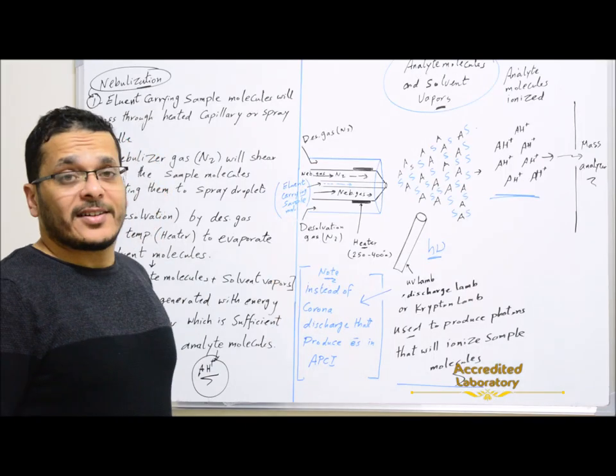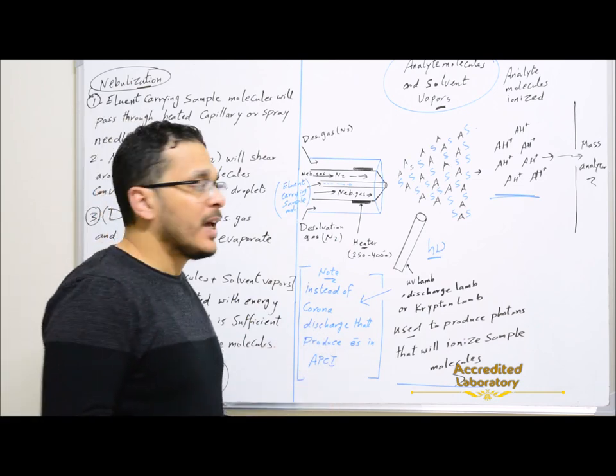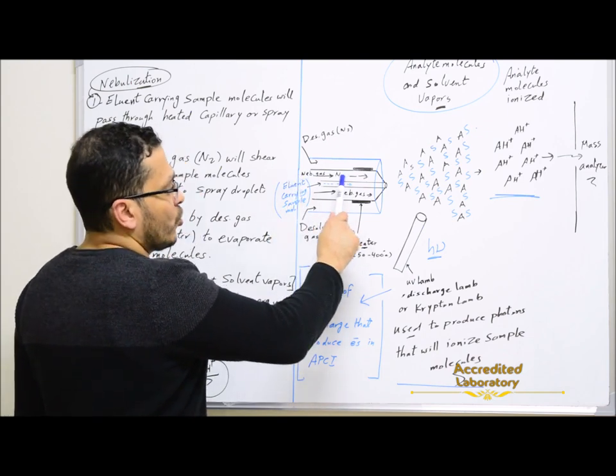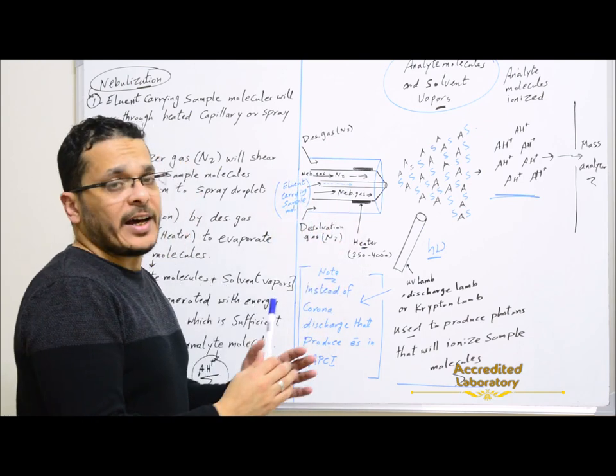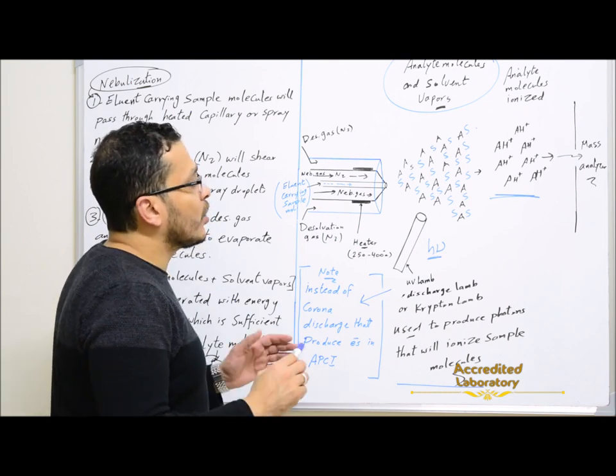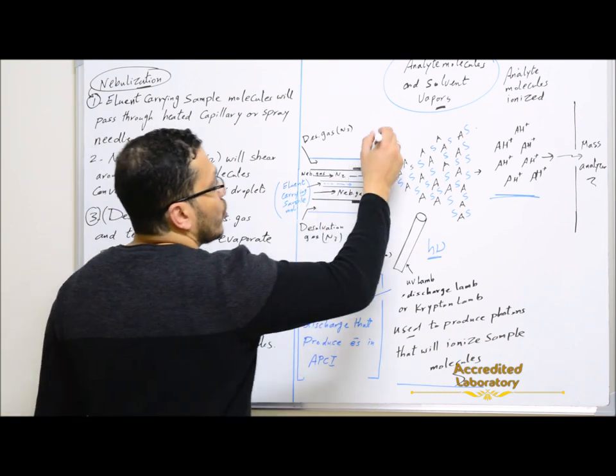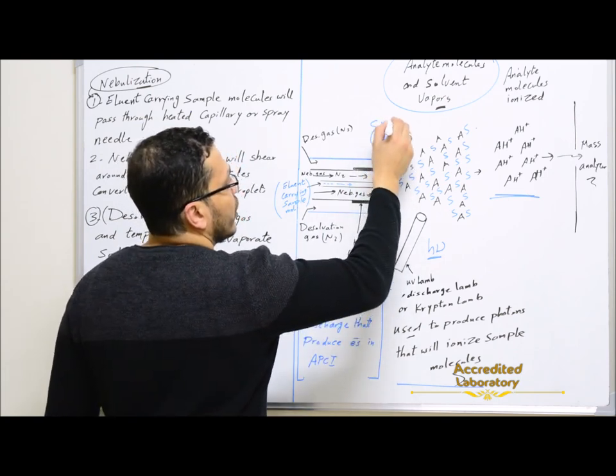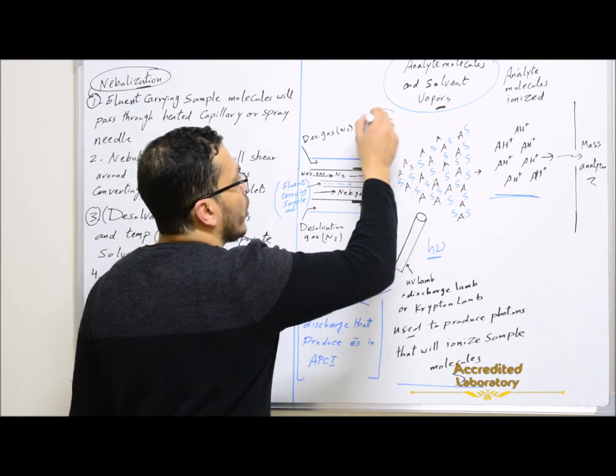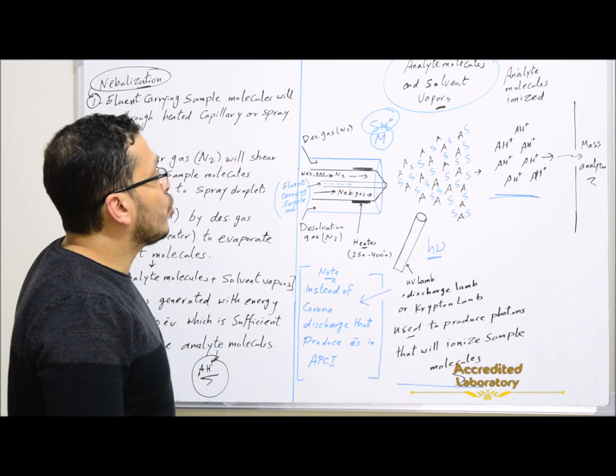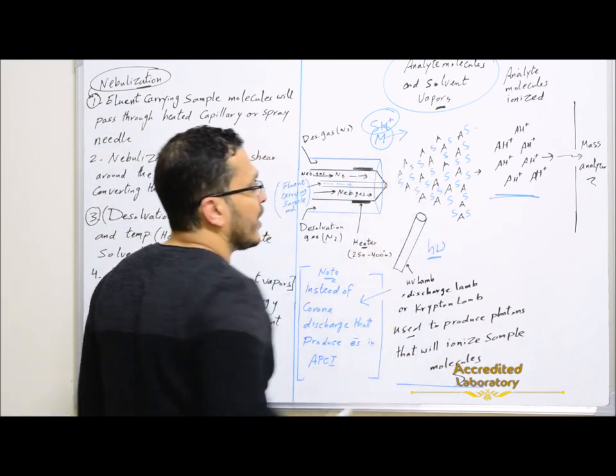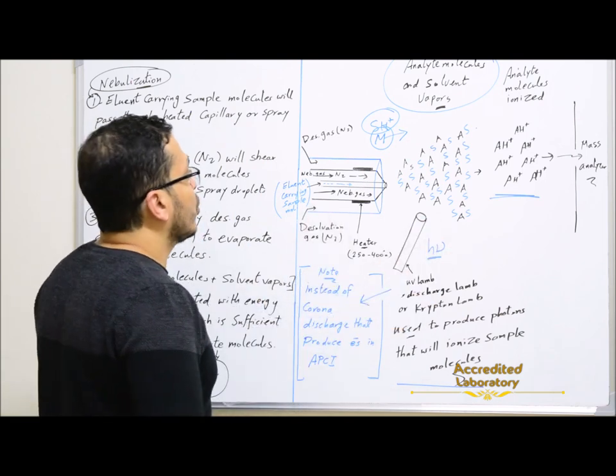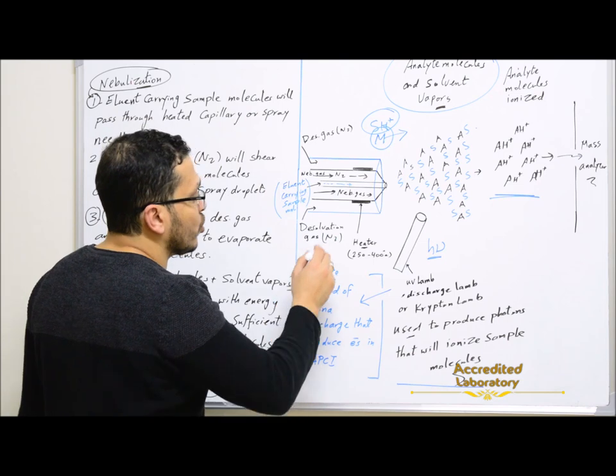The mobile phase from the HPLC will carry the sample and it will be transferred through the spray needle. The nebulizer gas, or nitrogen gas, shears around the eluent carrying sample molecules, nebulizing them to spray droplets which consist of sample molecules surrounded by solvent molecules. We need to evaporate the solvent molecules to get only the analyte molecules that will be ionized to get analyte ions to be transferred to the mass analyzer.